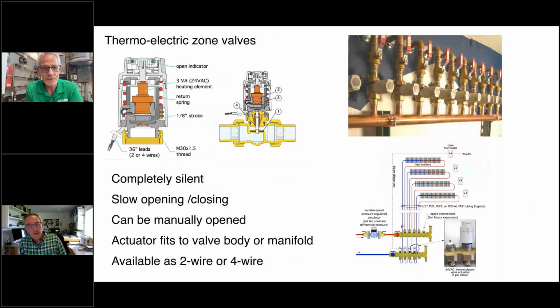Yep. Real quick too, and I'm going to keep moving. Thermoelectric valves. These are basically heat motors. They do operate on 24 volts. The features of them, they are completely silent. They are slower. Depending on the surrounding air temperature, they can take 2 to 3 minutes to open. You can open these valves manually simply by twisting the knob, the top of that actuator. And the same actuator fits either a valve body like what is shown here and in this photo, or it can be screwed onto a Caleffi manifold valve.